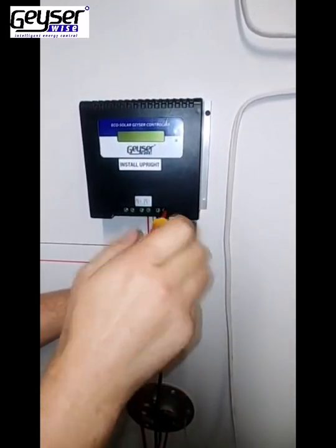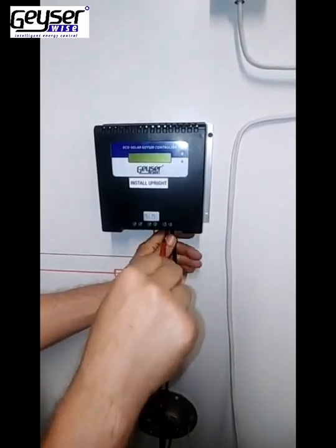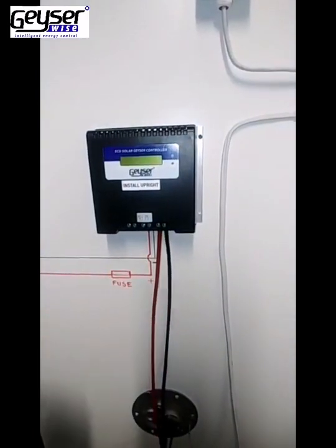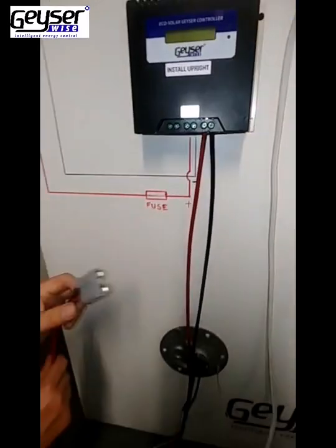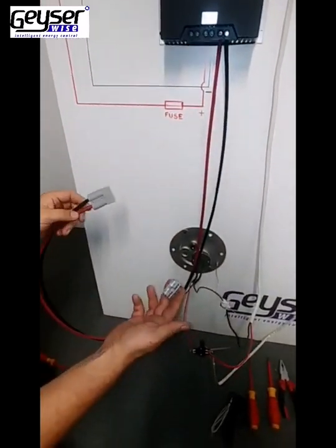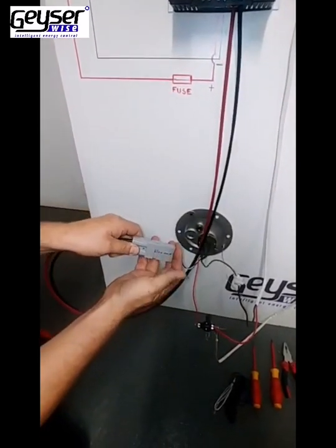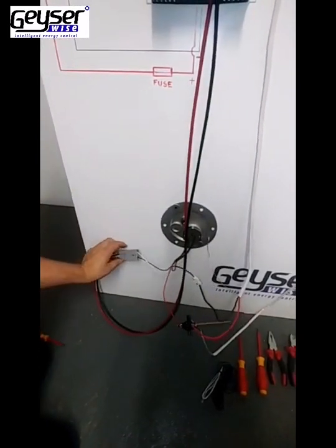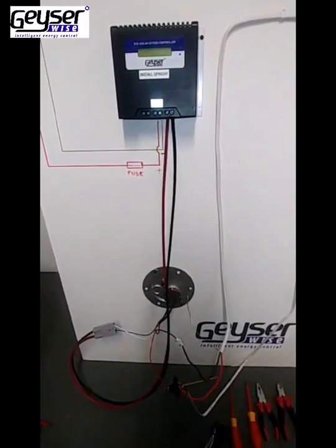This is marked on the MPPT Controller. Also ensure with the MPPT Controller that you don't exceed 138 volts open circuit voltage. On the other side of the MPPT Controller you will see there is an Anderson connector, and on the DC side of the element there will also be an Anderson connector. The one simply plugs into the other, and that is how you connect the hard wiring of the GeyserWise PV Water Heating System.